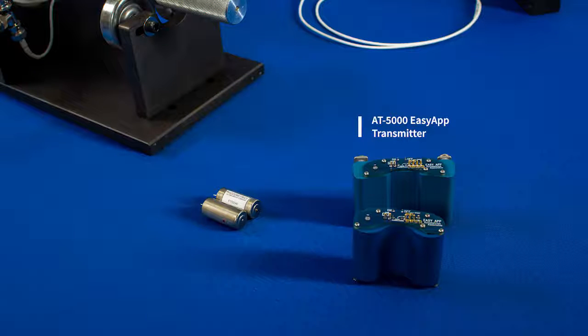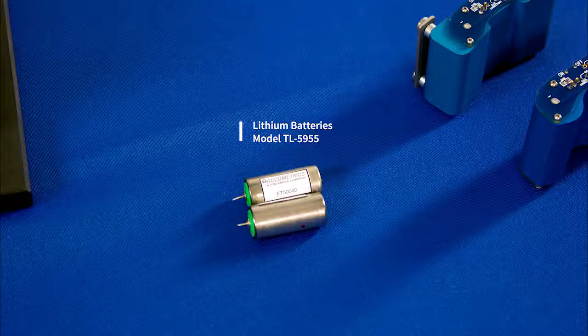The transmitter is small and available in three different housings to accommodate various shaft sizes. Its height is less than one inch to minimize radial clearance needed for the system. Battery life varies depending on the resistance of the strain gauge being used and can range from 75 to 95 hours in continuous use.